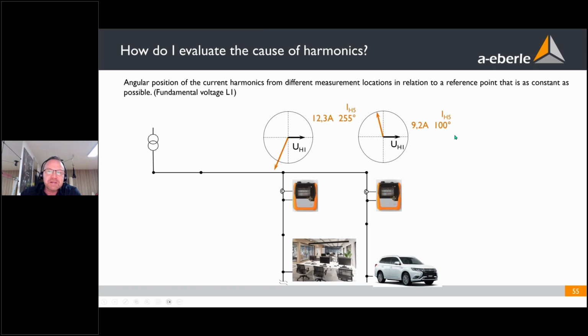But our analyzer provides a phase angle. We know exactly where the current is at the moment. And if you add both, the sum for the transformer at the moment is only 5.6 amps. So if you switch off even one of these producers of harmonics for the transformer, it goes up. So with this information, we can work much more clearly.